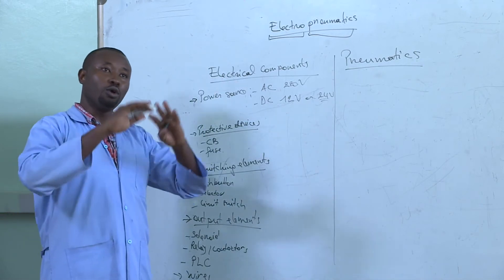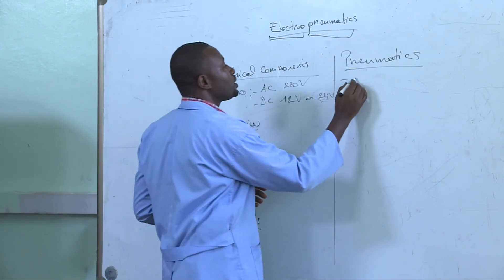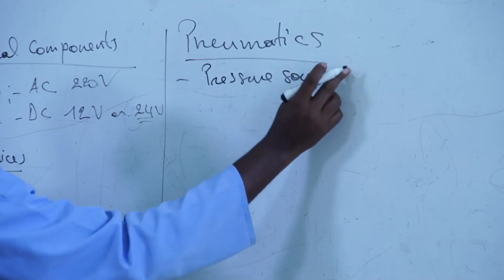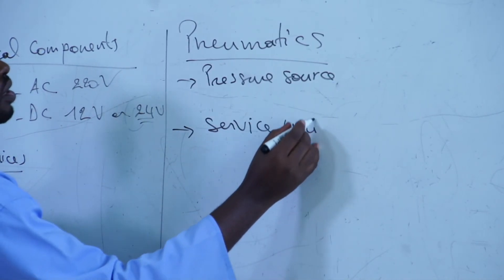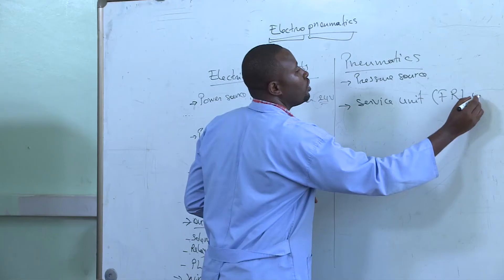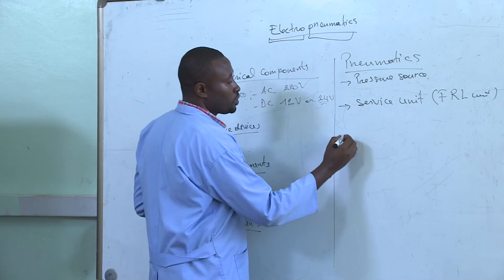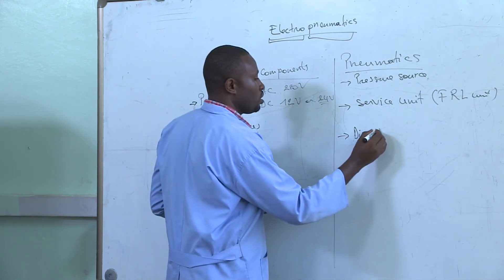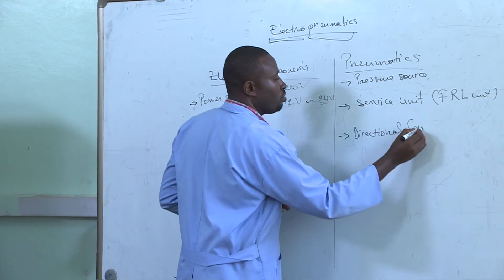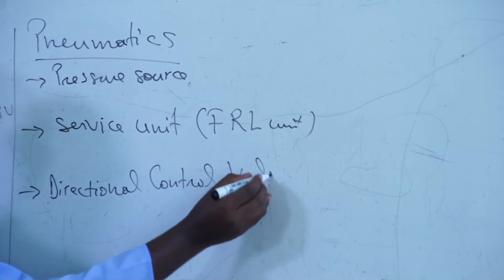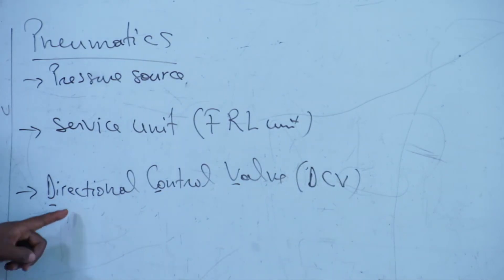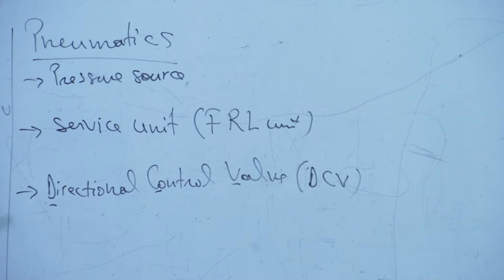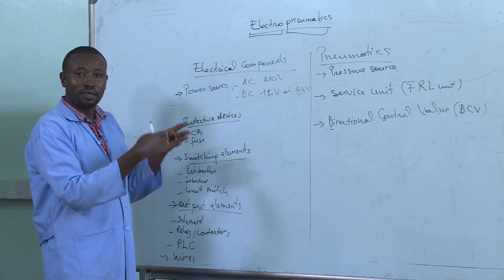On the pneumatic side we will need a pressure source. We will also need a service unit, also known as an FRL unit. We will also need a directional control valve, also known as a DCV. The directional control valve is electrically controlled by the solenoid, so the connection between the electrical and the pneumatic sides will be done at the directional control valve.